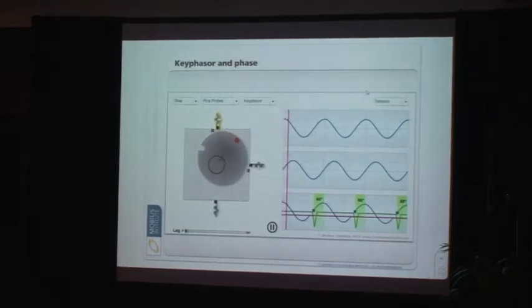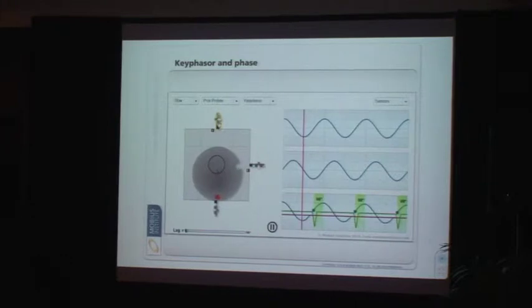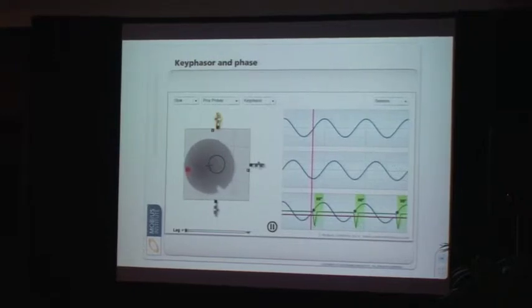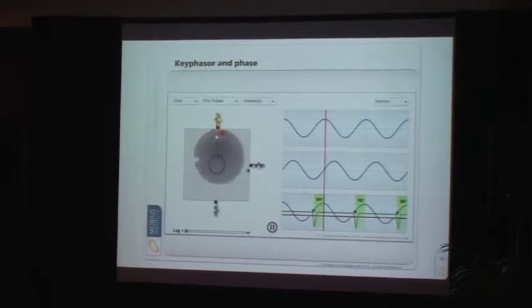Now, when we take our phase readings, this is basically what's happening. The shaft's turning, here are my two time waveforms. This one relates to this probe, this one relates to that probe, and then we've got our timing reference. If you watch for a moment, the keyway goes past this probe and triggers it, there's the little dot, and then it waits until the heavy spot, or high spot, let's just keep it simple.